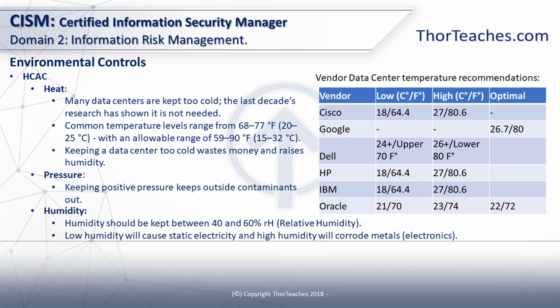Too low humidity will cause static electricity, which as we know can damage our equipment and corrupt our data. And too high humidity will start to corrode metals, which most of our servers are made of, so that's a really bad idea. In our HVAC systems, an integral part of those is both a humidifier and a dehumidifier to ensure we operate in that optimal range for humidity.